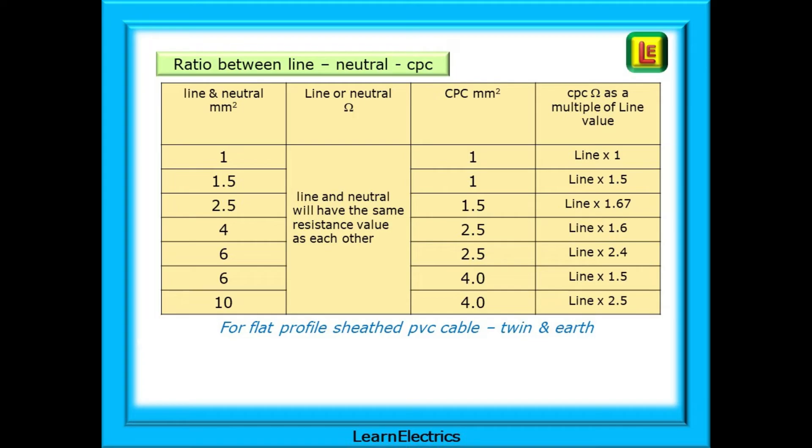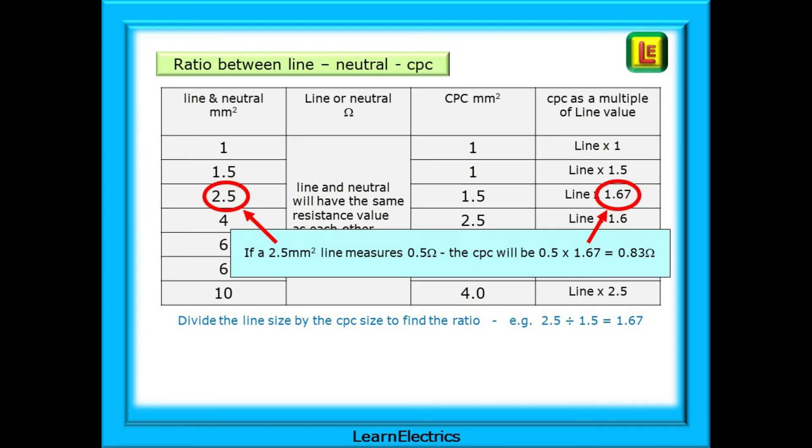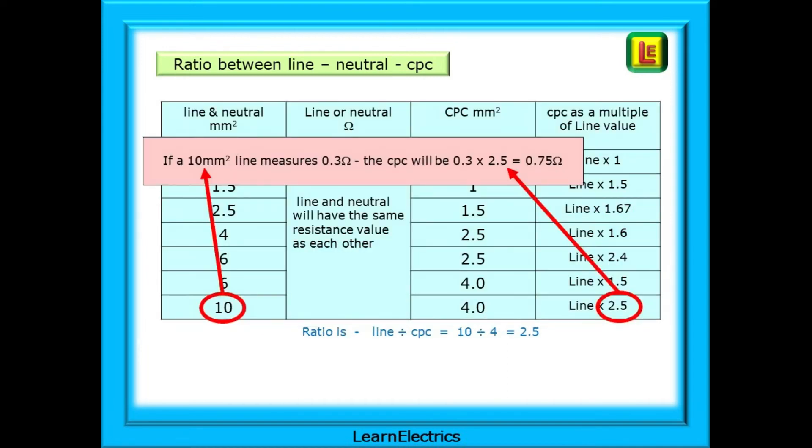To use our current example, if a 2.5 mm line measures 0.5 ohms, the CPC will be 0.5 multiplied by 1.67, which is 0.83 ohms. And if a 10 mm line measures 0.3 ohms, the CPC will be 0.3 multiplied by 2.5 to give us 0.75 ohms. All we have done is divided the line size by the CPC size to get the multiplication factor. This works for any sizes of conductor.